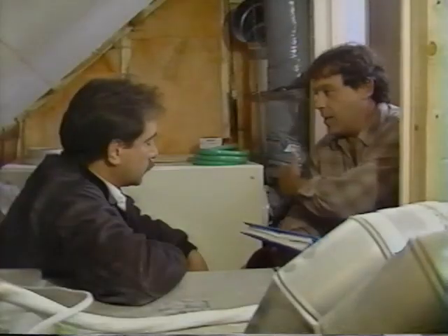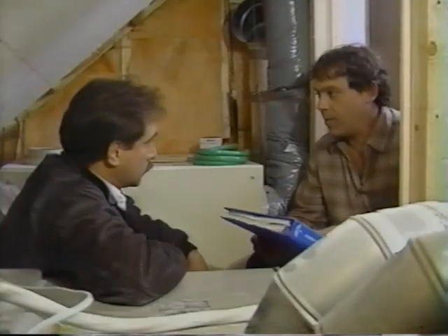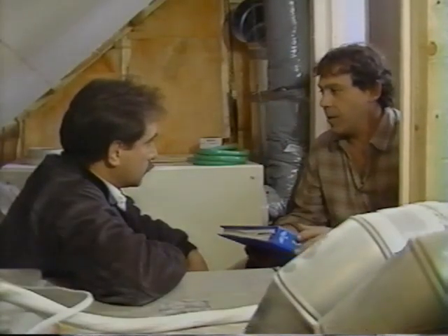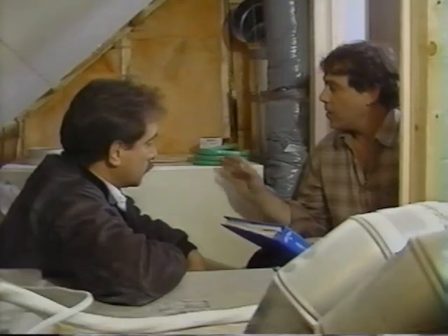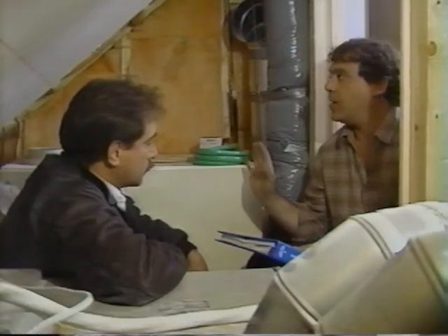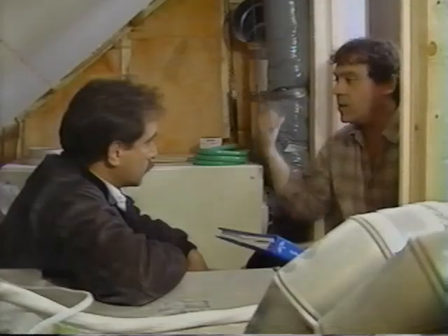Okay. That kind of centers around the ductwork that goes from this unit to the outside because it's an insulated, flexible ducting. It's insulated because the air in those ducts is cold and you don't want the humidity in this room to condense on the outside of those pipes and be a problem. But as I understand it, this stuff kind of restricts airflow a little bit, and it's also expensive. So you locate the unit centrally, but near an outside wall to minimize the runs of that. Right. The name of the game is the best airflow, the best installation we can get for the least amount of money.